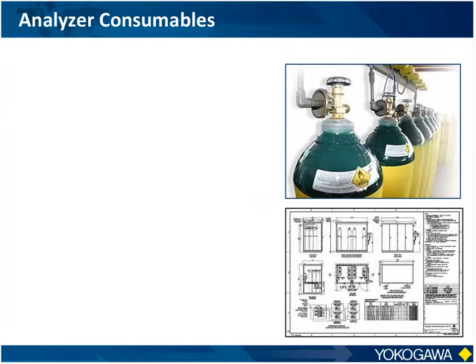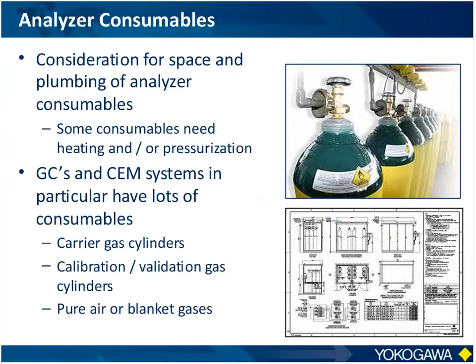Analyzers themselves tend to have a lot of consumables. These can include things like carrier gas and calibration gas. So when you do your design and layout of the shelter or cabinets or racks, you need to allow room for this because they need to be mounted somewhere and then plumbed in and brought in. And these are particularly true of chromatographs or environmental monitor systems, because they tend to have zero and span gases and validation gases and blanket gases and purge gases and such as this. And you can have a tremendous amount of bottles, like you can see in that upper picture there, that can be needed. And so you can almost have an entire wall dedicated to nothing but cylinders.